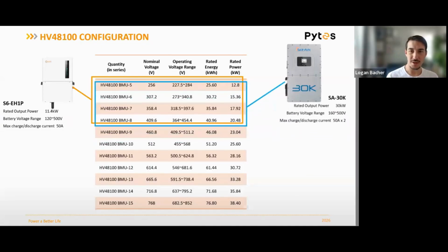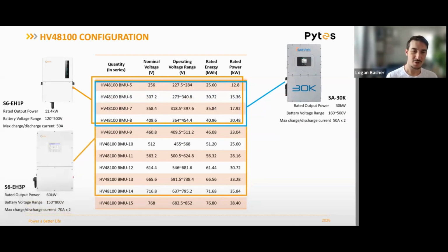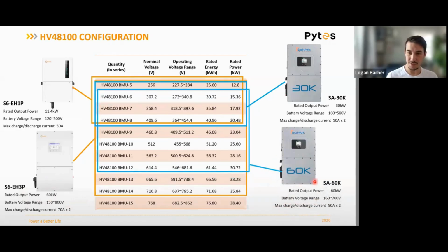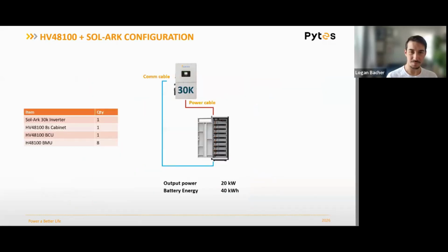So these are just the possible ways that you can configure the high voltage batteries depending on what inverter is being used. Today I'm focusing primarily on Sol-Ark and Solis. Those are our two main inverter partners and two brands that Charge Solar offers. You can see here, some of the models with the lower input voltage of only 500, we can only do about 8 batteries in series. The new Solis commercial hybrids are pretty nice because they have an 800-volt limit. We can go up to 14 batteries in series. And then our Sol-Ark 60K is right in between. That's 12 batteries in series as a maximum for that unit.